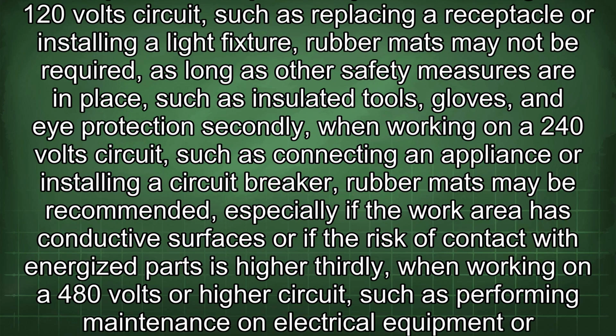To further clarify the relationship between voltage levels and the need for rubber mats, let's consider some examples. Firstly, when working on a 120-volt circuit, such as replacing a receptacle or installing a light fixture, rubber mats may not be required, as long as other safety measures are in place, such as insulated tools, gloves, and eye protection.